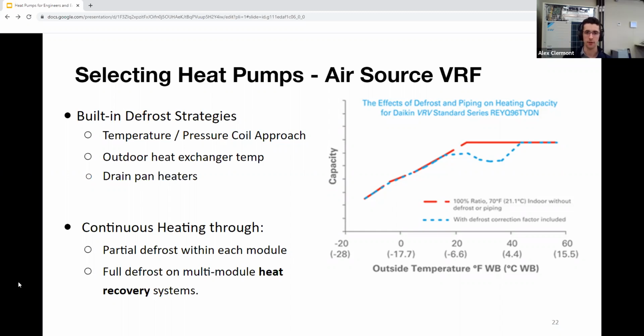Now, we want to talk about another factor, an accessory that's useful for these machines. It's those drain pan heaters. When a machine goes into defrost, it's trying to melt the ice off its coil and reject it away from the unit, all the way down at the bottom and away from the unit. When it does that, water tends to accumulate at the bottom of the unit. So drain pan heaters are often seen, and they prevent ice buildup by keeping the bottom of the unit warm, so ice doesn't form down there.